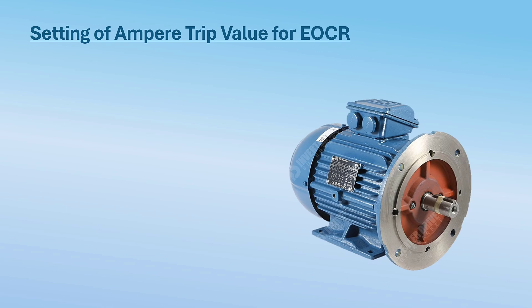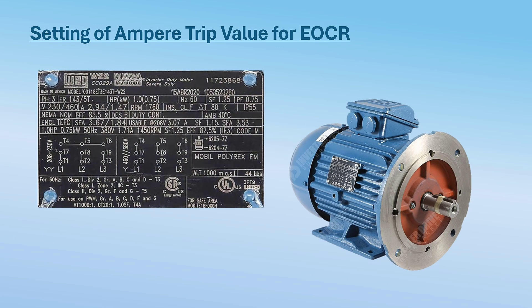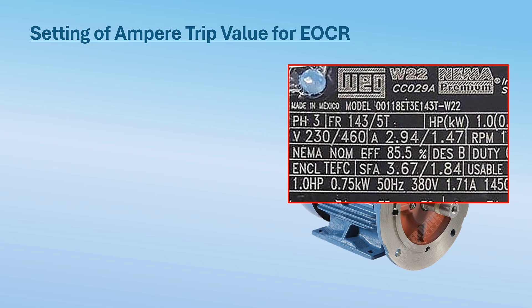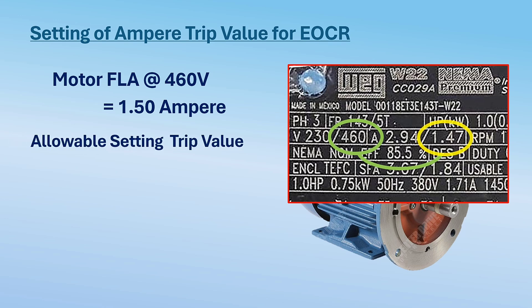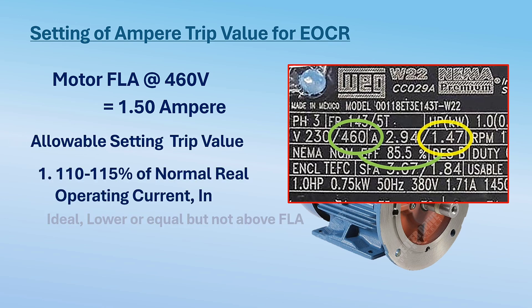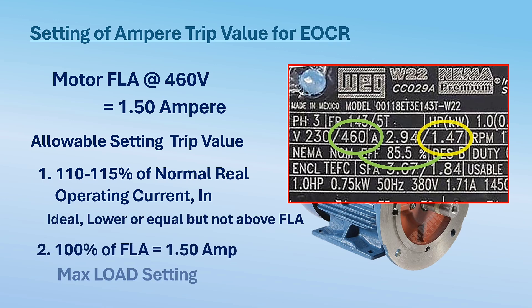Setting the ampere trip value for the EOCR: from the motor nameplate, the rated full load ampere or FLA is available. In this sample motor, it is a two-voltage motor — select the proper voltage and its equivalent FLA for your system. Since we are using 460 volts in this sample, the FLA of the motor is equivalent to 1.47 or around 1.50 amps. Ideally, set the EOCR ampere trip setting based on the motor's normal operating current, then multiply it by 110 to 115 percent. This should be lower than or equal to, but not above, the motor FLA. For this presentation, we will use 1.5 amperes as the overcurrent setting value.